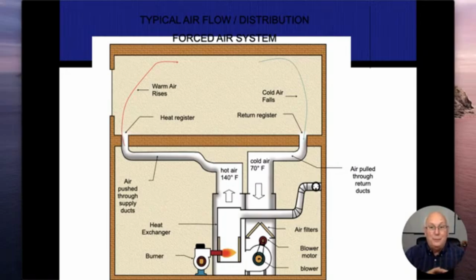The heat exchanger itself, if that's intact and there's no cracks, openings, or anything else in there, then there's no way for those bad gases to pass over and get into my circulation air. Safety feature number two. And then the third one is going to be my air pressure differentials. I have to have my blower fan before that heat exchanger because I want to create a positive pressure on the outside of that heat exchanger so that if I did have any openings, I'm going to lower or reduce the risk of carbon monoxide getting into my circulation air and then hence coming into my house.